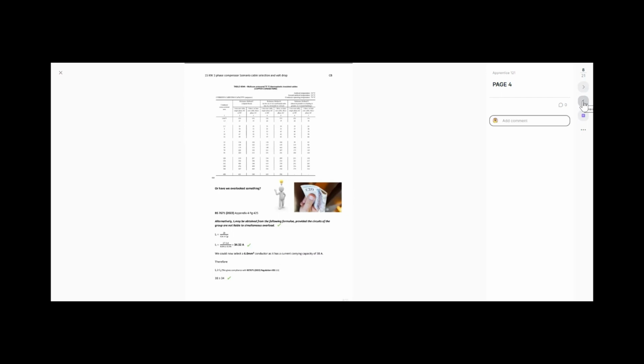Okay, good. So last week we had a bit of a moment where we've got to consider as well, Appendix 4 again, that statement that talks about you can calculate IT, but you can obtain it from a different formula, providing the circuits of that group, if they are grouped, are not liable to simultaneous overload. So circuits installed on its own. So I can use this formula instead to calculate the amount of current the cable is going to carry, but the only thing that changes is I'm not dividing the correction factors by the rating of the device because it can't overload. I'm dividing it by the design current, and the design current is 27.1 amps. You can never overload this thing.